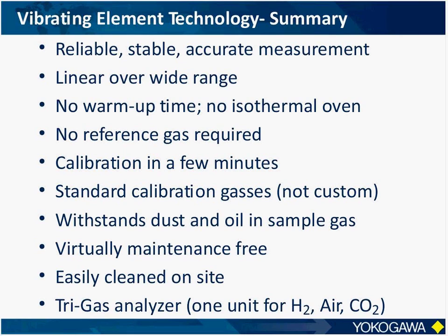Due to multi-mode oscillation, the analyzer withstands dust and oil in the sample gas fairly well, which allows it to be virtually maintenance-free. And in a bad situation where the detector itself is slugged with large amounts of oil or contaminants, it is easily cleaned on site and able to be put back in service without having to send the unit back to the factory for repair. And also, it's a tri-gas analyzer, which means for those power plant applications, only one unit is required to measure hydrogen, air, or CO2.